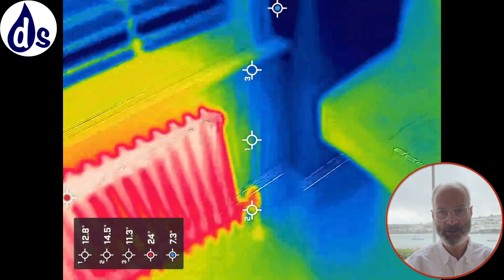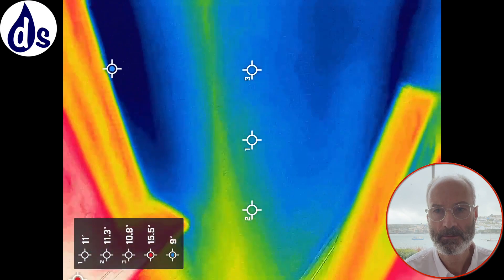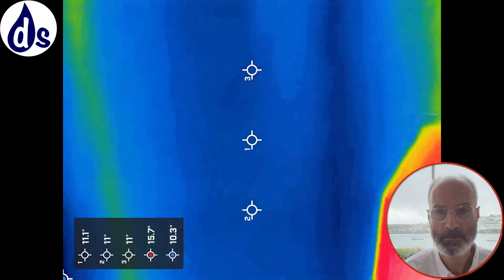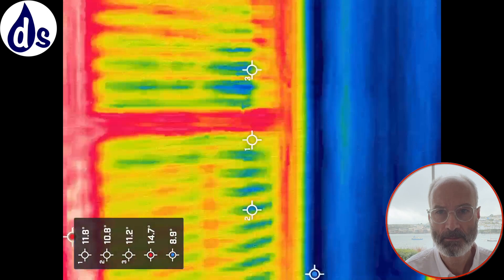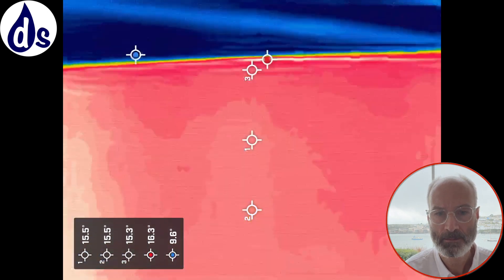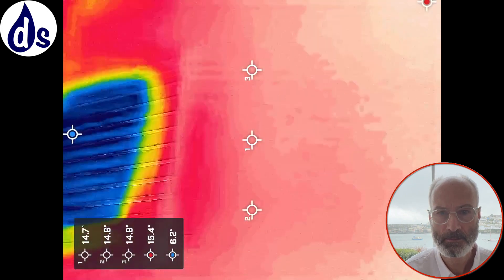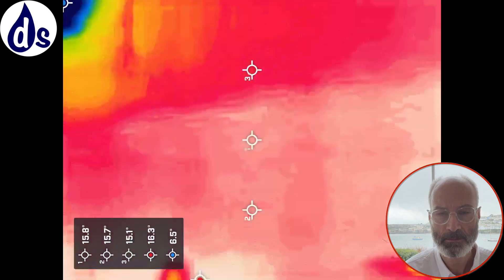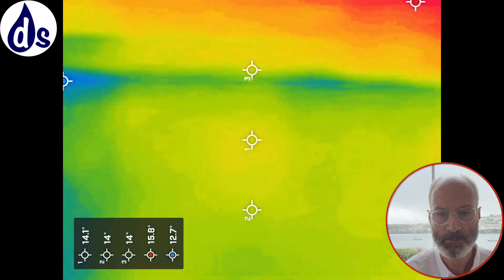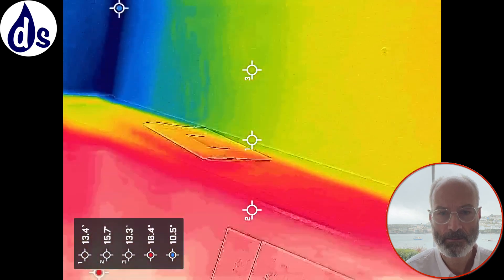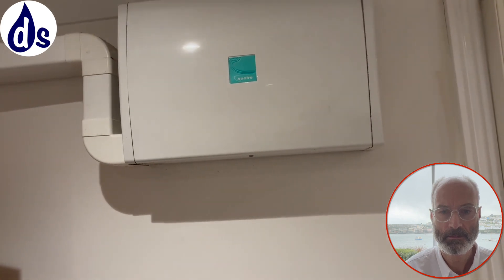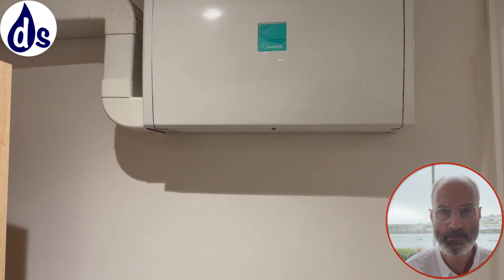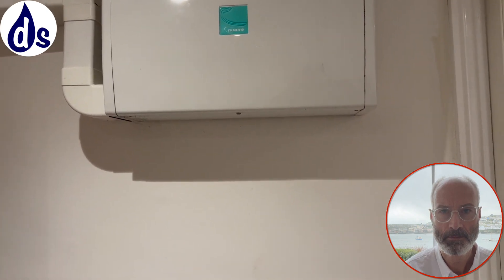This is looking through a thermal imaging camera — this is in the corner. You get a lot of heat loss there. Moving the piano out a bit would marginally help. You get a lot of heat loss from these things as well. Feel the cold air coming through. It's basically pumping in cold air and you're heating it up and it's coming through averagely rather than targeted, which is why I don't recommend them. PIV fans are not an alternative to bathroom ventilation and kitchen ventilation — they're for background ventilation. If you've got good ventilation and dehumidification, you don't need these fans.